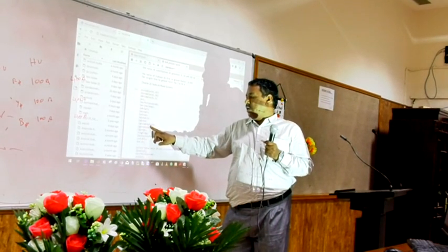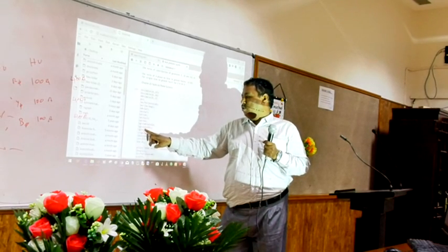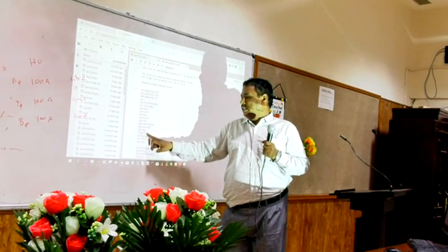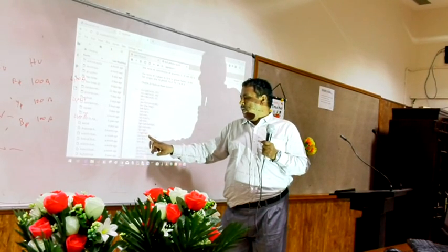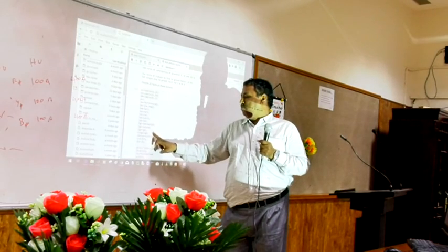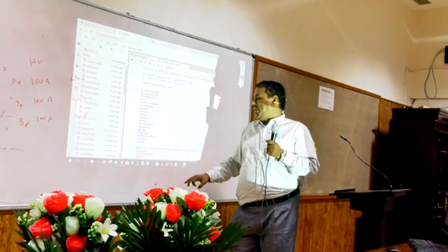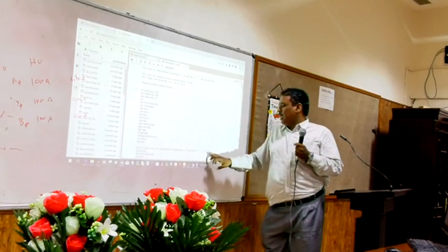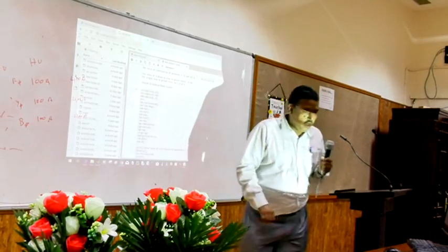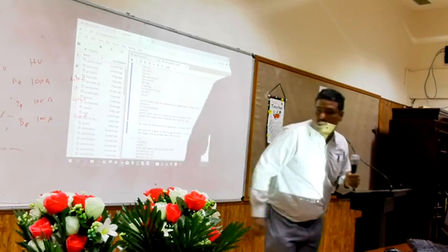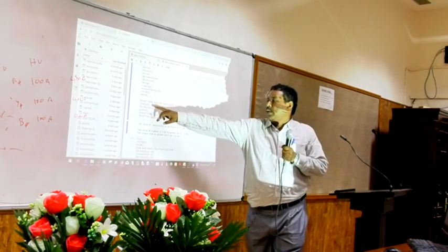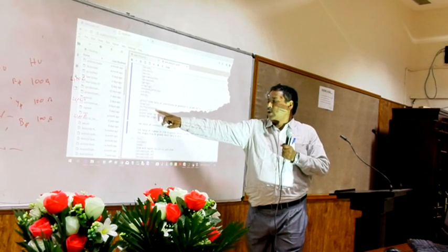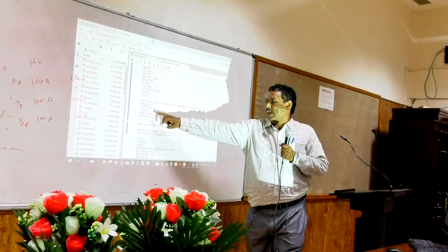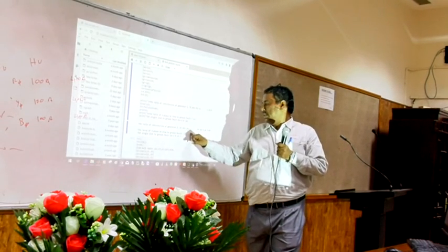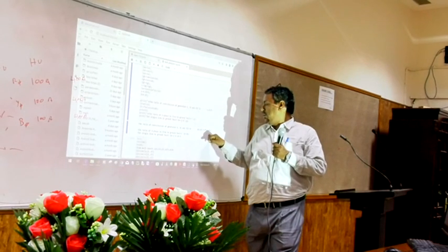IG1 equals IA0 plus IA1 plus IA2. IG2 equals IA1 plus IA2. IG3 equals IG2. So C equals IG1 divided by IG2. Then round off, so you are making a round off. C and D values are there. So printing the ratio of the contribution of generators 1, 2, 3, that is C, D, D. So printing the values. I3 equals E divided by x1, I1 equals 3E divided by x1 plus x2 plus x0, y equals I3 by I1. So the ratio of the contribution of the generators is 10.125, 4.05, 4.05.